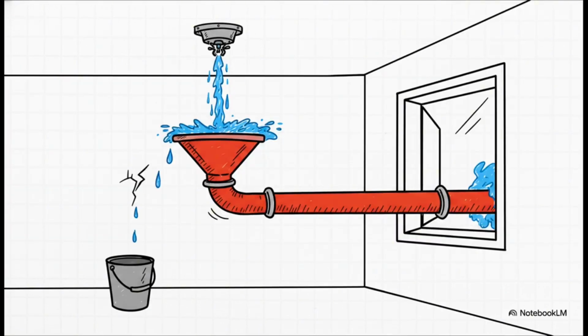But here's the gritty reality of salvage operations. Even perfectly placed wedges will still leak. You simply can't just walk away. Firefighters have to immediately manage that residual water to protect the rest of the property. For a small drip, they might simply place a bucket beneath it. If it's a larger, messier leak, they'll construct a catch-all out of heavy tarps. Or they'll set up a water chute to literally redirect the flow down a hallway. But honestly, one of the most ingenious, real-world methods they use is to just take a section of fire hose, hang it directly underneath the leaking sprinkler head, and run the other end straight out of a window or door, acting as a giant makeshift drain pipe.